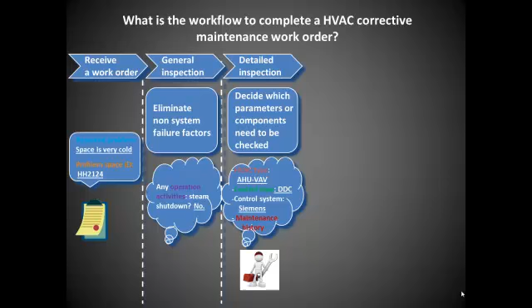After non-mechanical failure factors are eliminated, the mechanic will do a detailed inspection to decide which components or parameters need to be checked. He needs to know what type of HVAC system it is, how it is controlled, what building automation system it is using, and the maintenance history of this system and space.